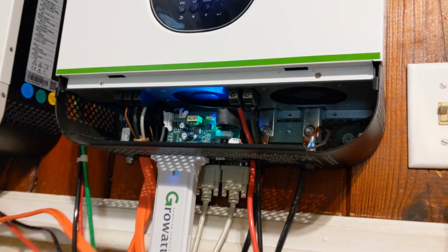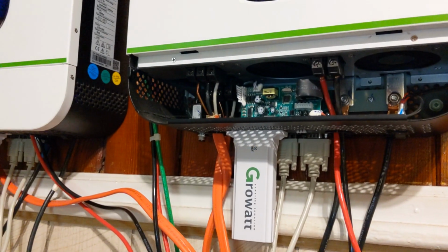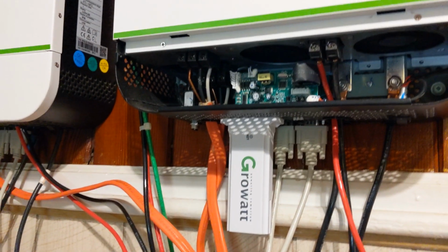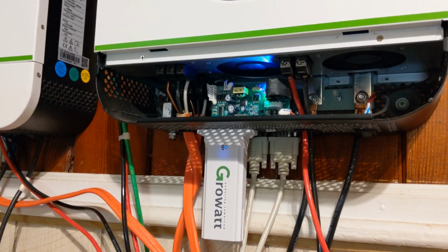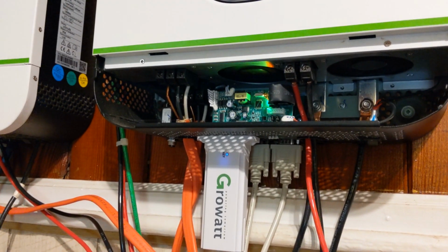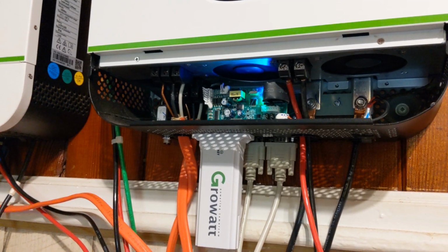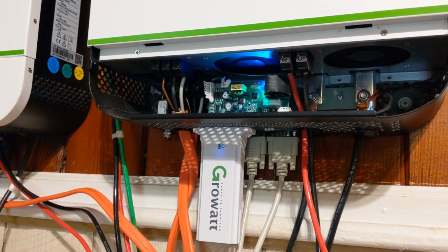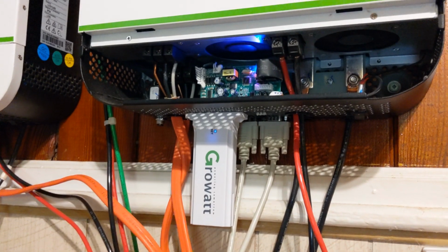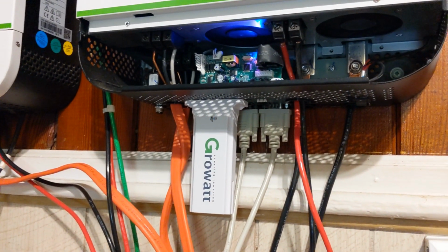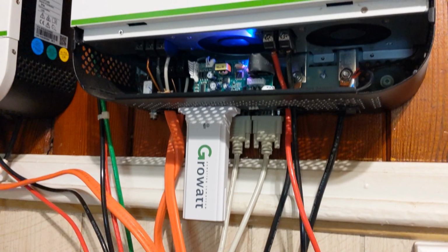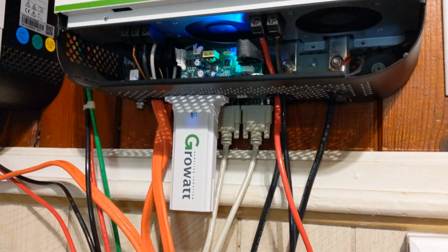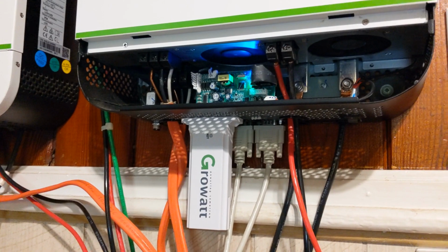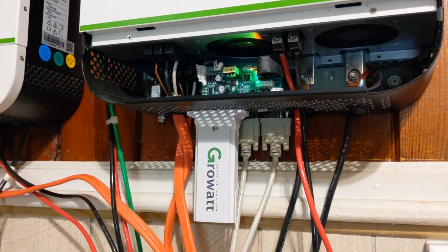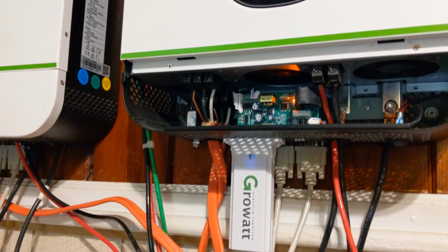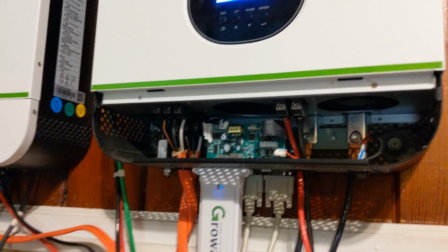The only issue I had initially was I connected up all the wiring, went to turn these guys on, and one of them was saying it had an error. Come to find out the dual pole split phase breaker in my panel, one of the two wires was not seated all the way in there. So one of the units was getting AC power, the other unit was not. It was recognizing that it was configured for split phase power but not seeing split phase, so it threw up an error code saying this is not right. It took me a little while to figure out it was literally a loose connection on this breaker. Once I fixed that, everybody powered up, and it's been running fine ever since.